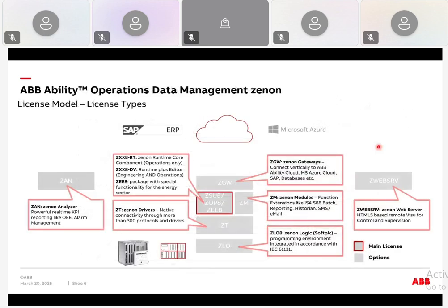When you select the Zenon modules, it is first based on the tag. We consider each variable as a tag, and if you have any physical IOs, those will also be counted as tags. When selecting Zenon based on the tag count with physical IOs, as a thumb rule, we calculate the number of physical IOs times 4.